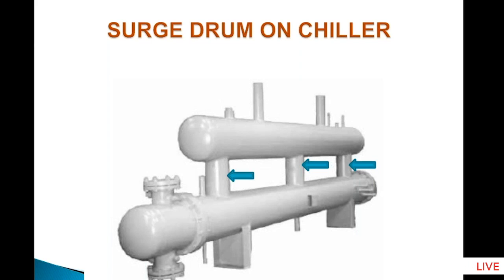What is required, just try to understand the theory. The liquid droplets are heavier than the gas and they will tend to fall down. So on the liquid droplet, there are two forces. One is gravity pulling down and the second is the compressor pulling. If the compressor pulling is higher, the liquid will enter the compressor. If the gravity force is higher, the liquid will fall down.